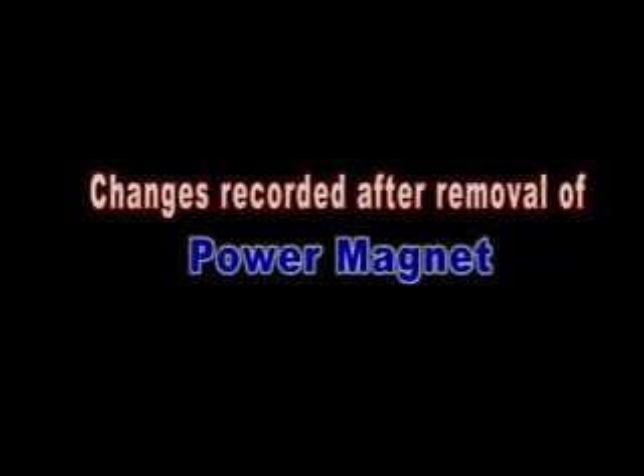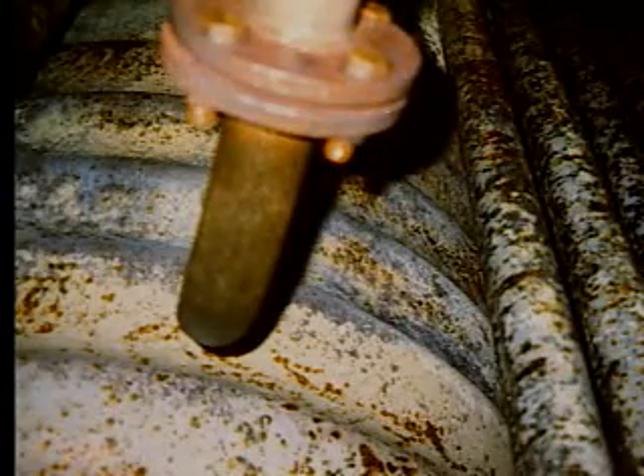New boilers already have serious rust before installing Power Magnet. After using Power Magnet for 130 days, corrosion improves even before cleaning with only a little rust remaining. At this time, there is already clear improvement of corrosion after washing. Pipe walls already start to display a protective Fe3O4 membrane. After using Power Magnet for 227 days, corrosion is completely removed before washing. At this time, the protective Fe3O4 membrane on the pipe walls can be clearly seen after washing. After factories removed Power Magnet and switched to using chemicals for 50 days, scales and slight corrosion could already be clearly seen. Because the factories discovered that there was already scaling and corrosion occurring, they increased the amount of chemicals used. After 110 days, there was no improvement in the scales or corrosion situation and it was in fact even worse.